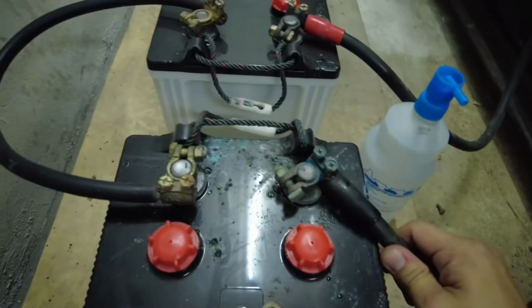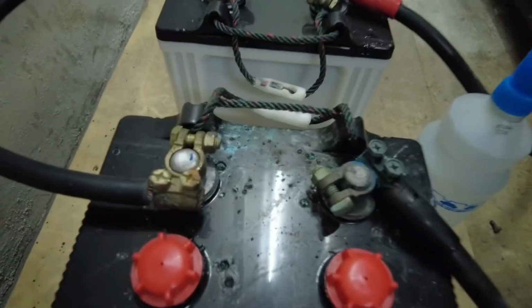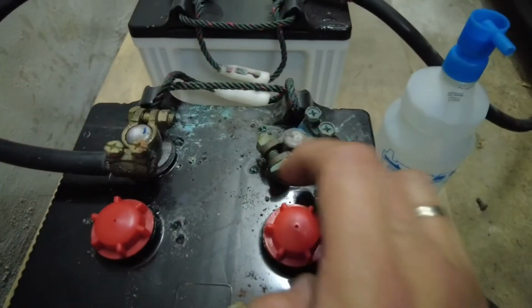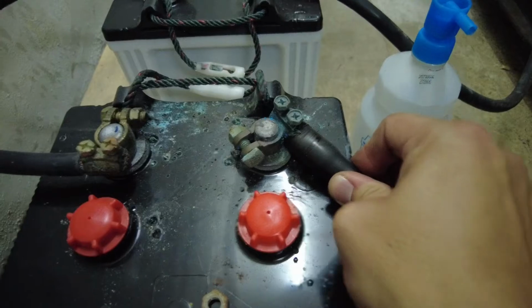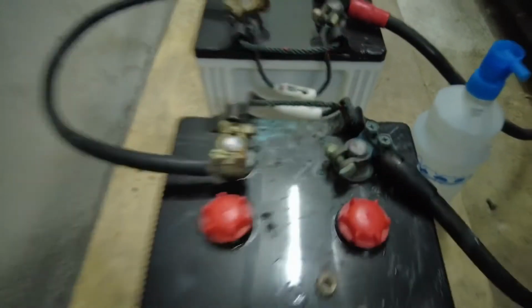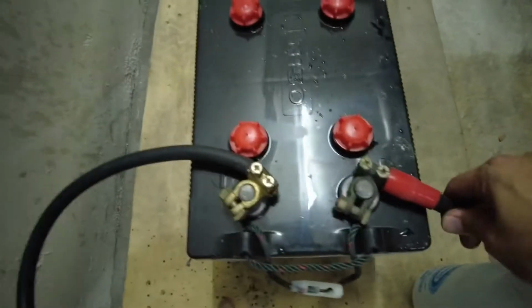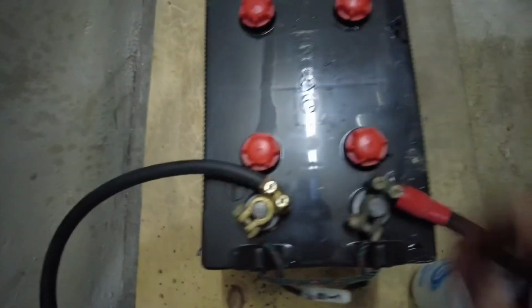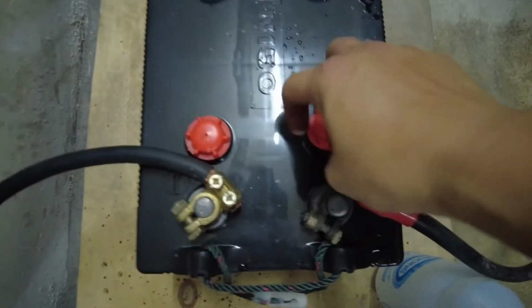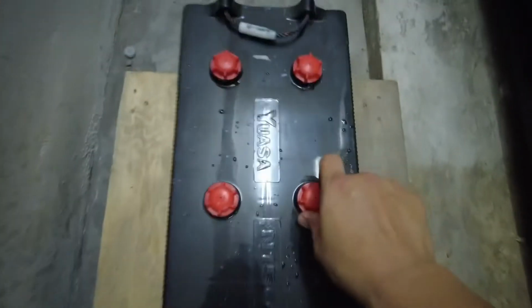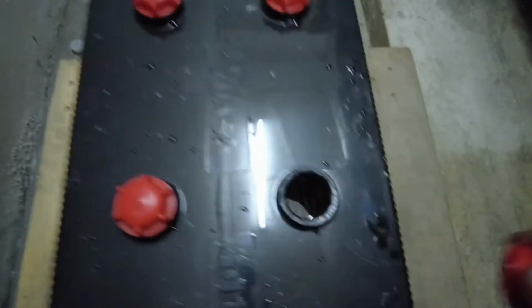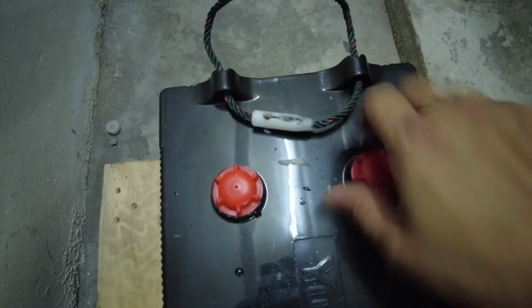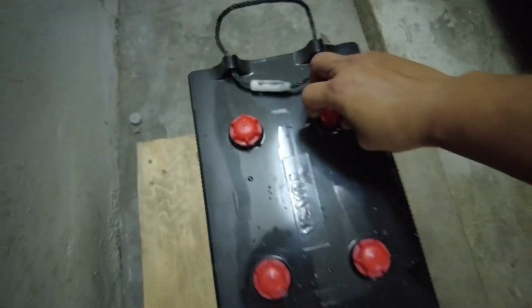Here we have a previous burn area. It's due to the loose termination. However, now it's okay. That's why you must always make sure the battery termination is in tight condition. During the starting, a few hundred amp pass through this cable, so it's very important to make sure it's tightened. All cells are in good condition.